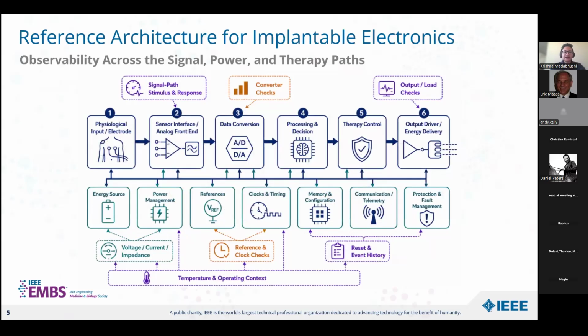So here I'm showing a simplified architecture, which gives us a useful way to organize this problem, right? The main signal path begins with the physiological input from the electrodes. That signal moves through the analog front end, then through the data conversion, and then there's the processing and decision logic. If a therapy is required, the system then moves through the therapy control and the output and energy delivery stage. Supporting the main path are the energy source, the power management, voltage and current references, a few clocks and timing, memory and telemetry, and some protection logic near the electrodes. Each of these areas gives us an opportunity for observation.